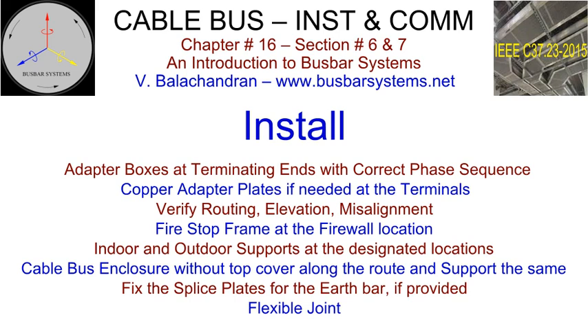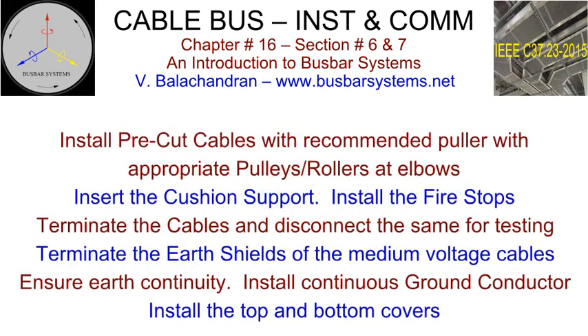Install the cable bus enclosure without top cover along the route and support the same. Bottom-most cable support is fixed at works before dispatch. Fix the splice plates for the earth bar if provided. Install the flexible joint if provided. Insert the pre-cut cables from one end using the recommended puller depending upon the length and diameter. Appropriate pulleys/rollers shall be used at elbows. Ensure that the cable sheath does not suffer elongation or external damage.